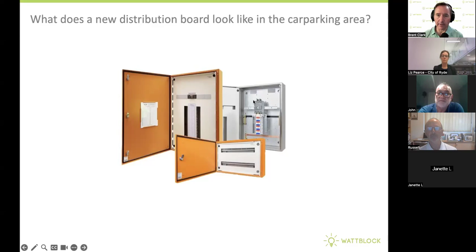The Altair is a building over at Potts Point. They've enabled EV charging for 165 car spaces, with 6 new distribution boards, one on every level of the building. They've got a dynamic load balancing system, Wi-Fi, and also a method by which the owners corporation subsidises the last mile cable run costs, so they're always equal regardless of how far you are from the nearest distribution board. Here you see some cable tray, an EV charge point coming off that cable tray, conduit up to the cable tray, then the cable runs along that. Here's the load balancing system in the main electrical room.